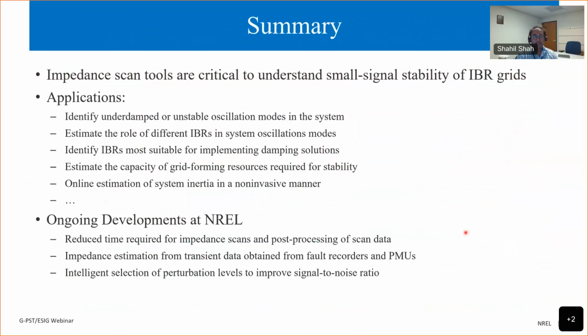So this is my last slide. I would just say that impedance scan tools are critical to understand small signal stability of IBR grids. It might be debatable whether we use them for all types of small signal stability issues, or we still depend on standardizing controls for slower control interactions where it is possible to standardize certain things. But we'll still need them for a little bit higher frequency, about 5 or 10 hertz, where it is very hard to standardize controls and also to model them, because the control codes are driving the behavior, not physical equations, as in the case of synchronous generators. I talked about all this part.